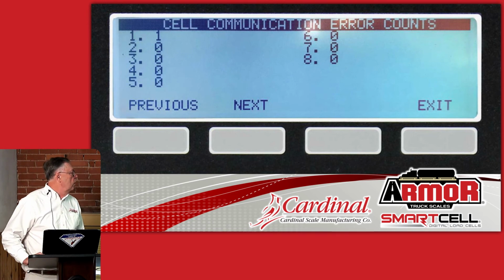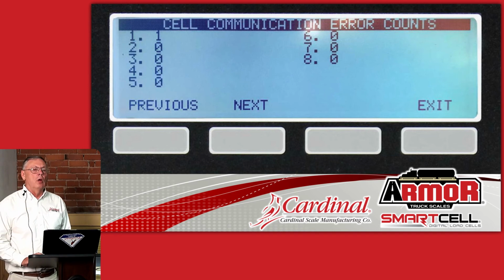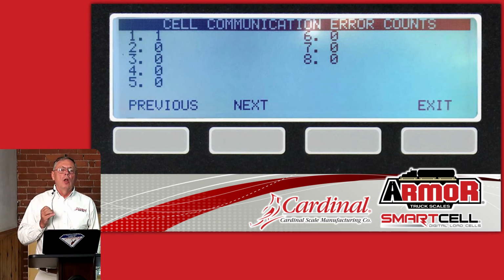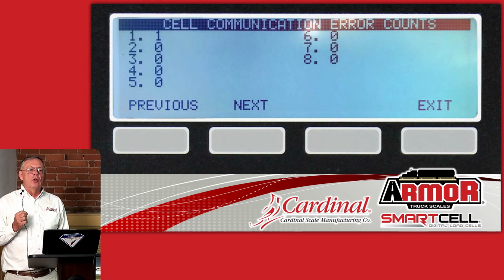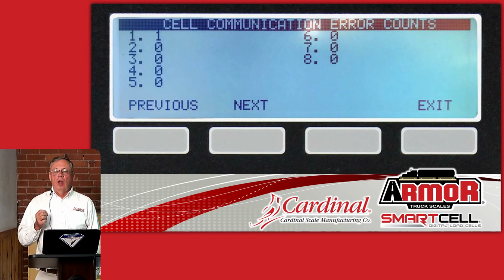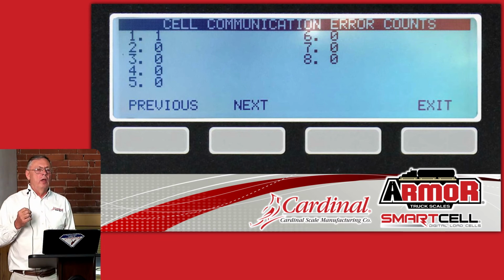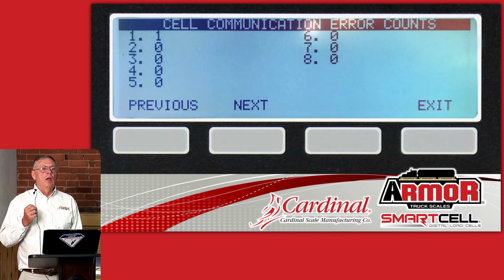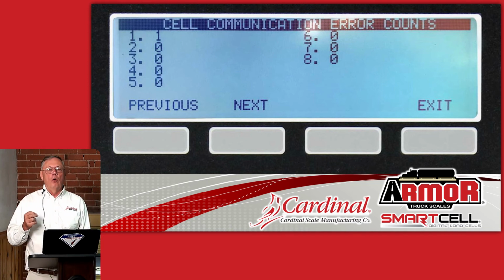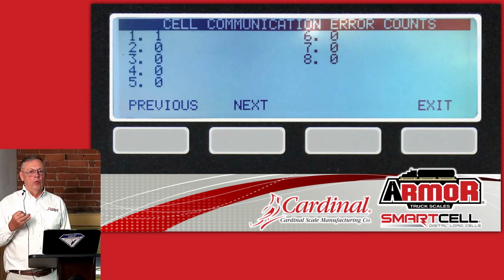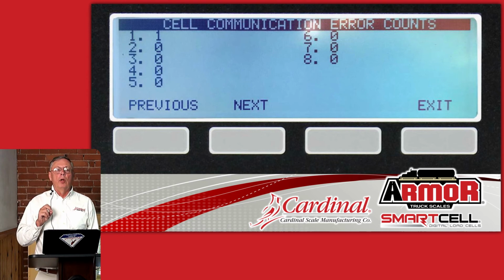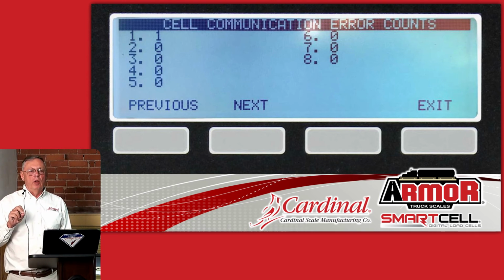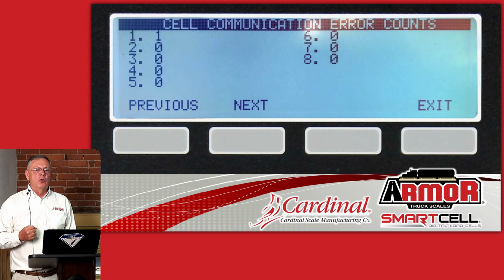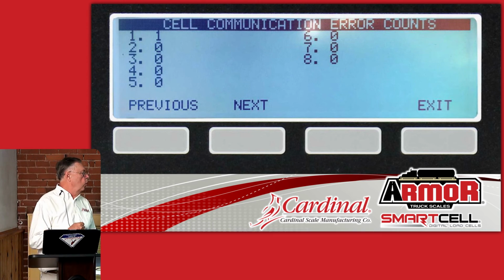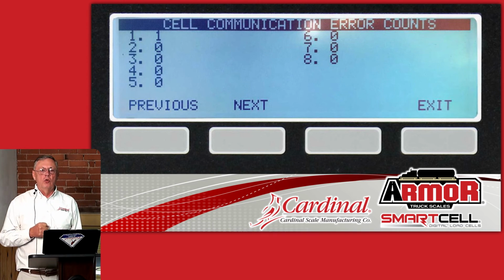Here we've got a screen that is showing load cell communication errors. With our digital load cells, a technician can't use a voltmeter to test that load cell. All we get out of the load cell is basically X's and O's, high states, low states for a digital signal, and we know we're putting about 14 volts into it. There's not much a technician can do to troubleshoot that load cell. We have to be able to tell him when there's an issue.